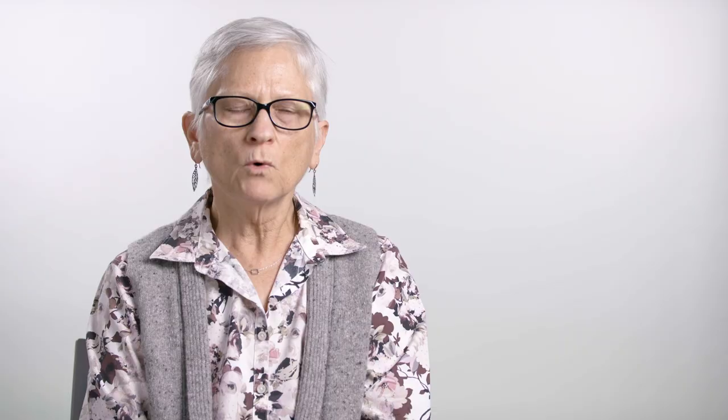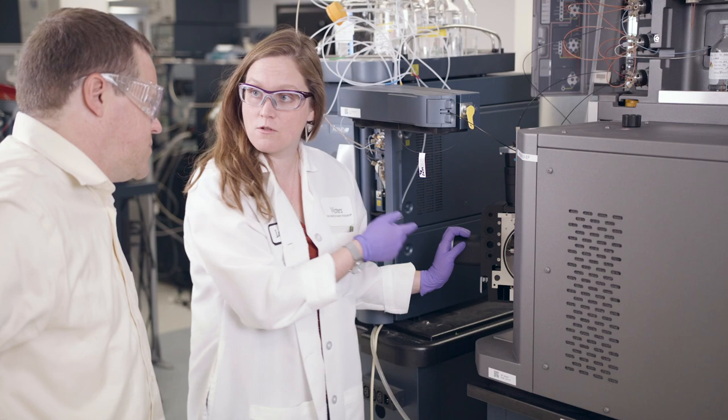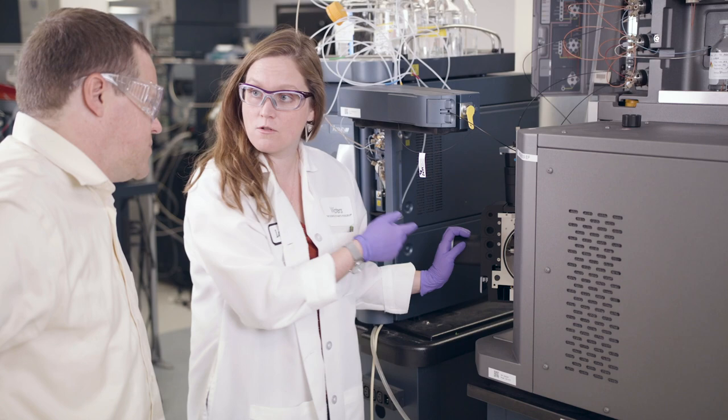The basic compounds would end up tailing a lot under these mobile phase conditions. Even though these were very high purity column surfaces, it wasn't just our brands of C18 that had this problem — you saw it everywhere. What was happening with the formic acid mobile phases is that the peak tail was more like a shark fin, and this was a problem for mass spec applications that required a larger dynamic range.